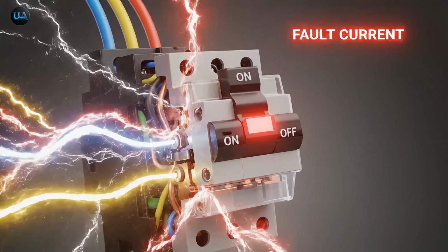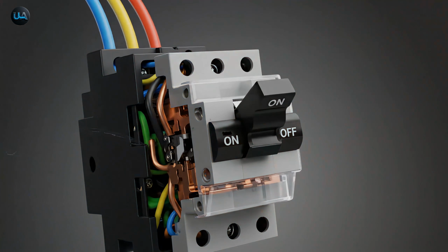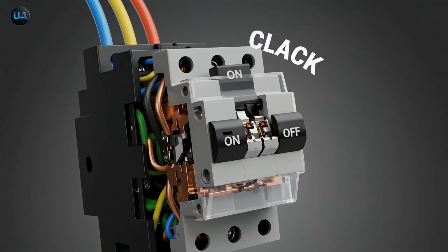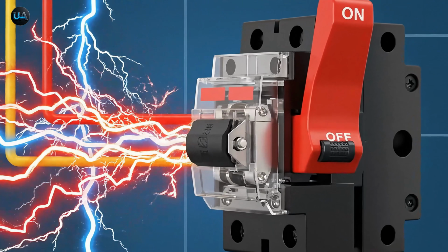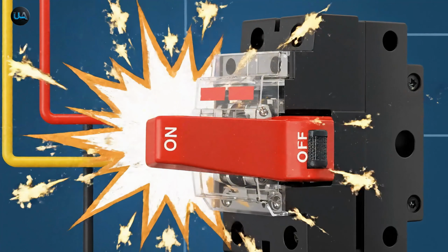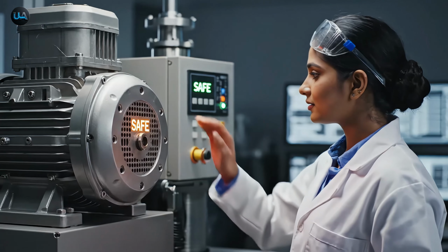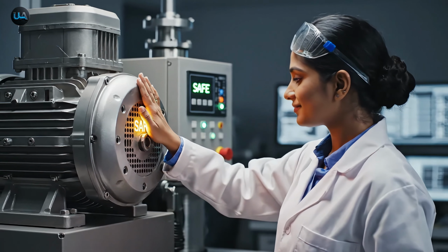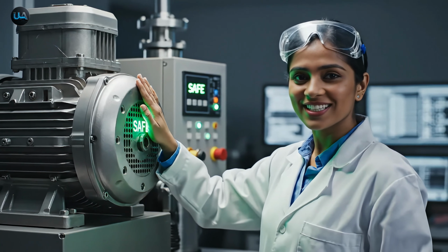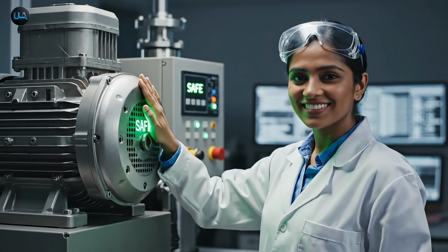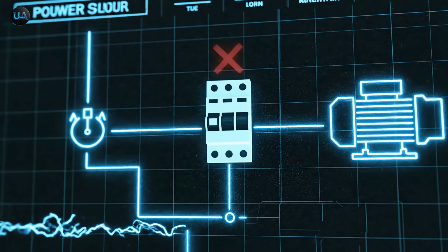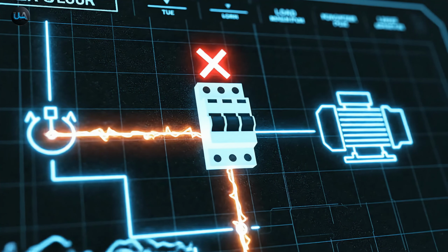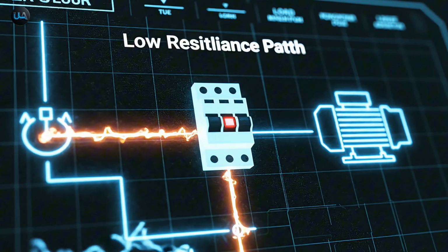This massive, intentional surge of current immediately trips the nearest circuit breaker or blows the fuse, instantly disconnecting the power to the faulty device. This rapid interruption removes the electrical potential from the casing, saving the life of any operator who might touch the equipment. The speed of the trip is crucial. The ground path must have the lowest possible resistance to ensure the fault current is high enough to trip the breaker immediately.